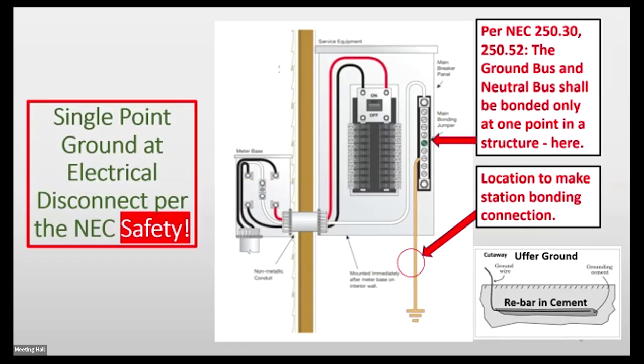On the lower right side, you'll see something called a Ufer ground. This is commonly used to cut corners and reduce size—they don't put a post or steel ground rod in. Instead they connect to the rebar in the foundation underneath your house, because the National Electric Code doesn't require the same kind of ground for electrical as it does for RF or lightning. So they use the rebar. I found that to be the case at my house, and that was part of the problem we had. When you get to the end, I'll show you how many ground rods I now have to install to replace that.